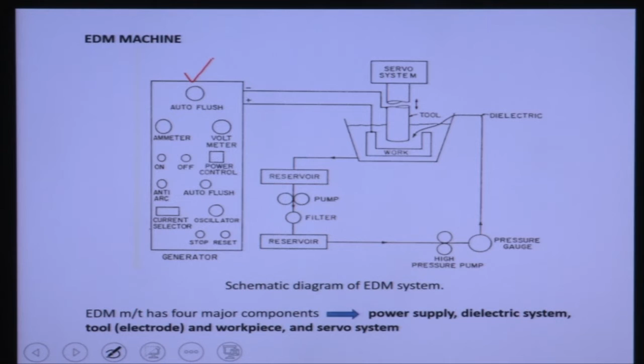So, a good dielectric fluid has the following properties. It should have high dielectric strength, so it should not break down easily. It should remain electrically non-conductive with a very high voltage, high potential applied, until the required breakdown voltage between the electrodes is attained. Then it should take minimum possible time to break down.